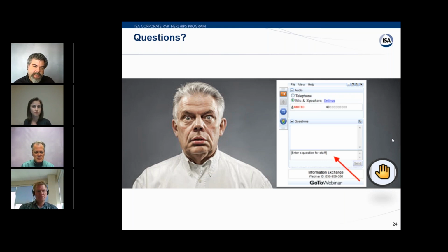One thing I found interesting in my testing is that going from a lower pH up to a higher was a lot faster, and I'm sure that had to do with the first session that you talked about. But if I go from 10 down to 4, it wasn't just a minute or two, it was a good 10 minutes to get down to where it needed to be and finally stabilize. So is it common to always go from a lower to a higher pH number? Is there a standard on that? Yeah, normally you start at the bottom and go up, just for that reason. It takes a lot longer to reverse, and I think it's just the shock of it, right?